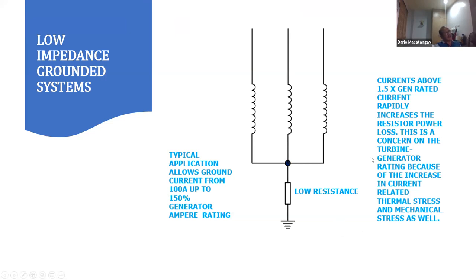Okay, so this one is easy. Using a low resistance, since you can generate 100 amps, you might be able to use an overcurrent relay and get good sensitivity and good protection coordination. Now, if you are using differential protection, you compare the current coming in and out of the CT. You might be able to do that, but again, this is only 100 amps.